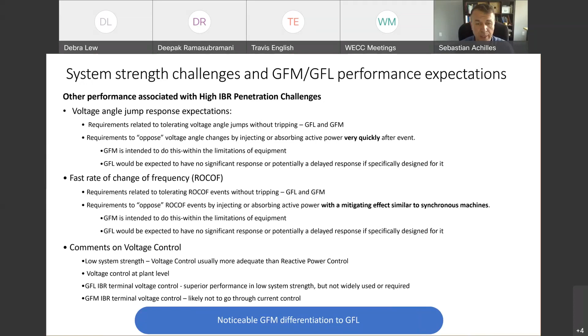So potentially there may be some additional advantages of terminal voltage control with grid forming with respect to grid following. But the bigger jump of advantages is a grid following IBR with terminal voltage control with respect to a grid following IBR without terminal voltage control. So there is a risk that in this discussion about grid forming, we get confused with improvements that you can have within the grid following concepts, like that is what grid forming is going to solve. Voltage control is the particular area where that confusion could happen. Can we move to the next slide, please?